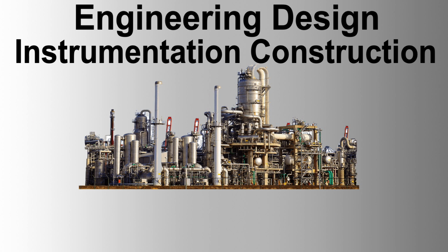Threads for screwed fittings are specified by the company. Contractor must ensure that the specified thread and thread sealants are used. The number of joints in pipework shall be kept to a minimum consistent with good practice. Where modifications are made to existing pipework or tubing systems involving threaded joints, it is essential that traces of previously applied sealant are removed from threads before the connections are remade.